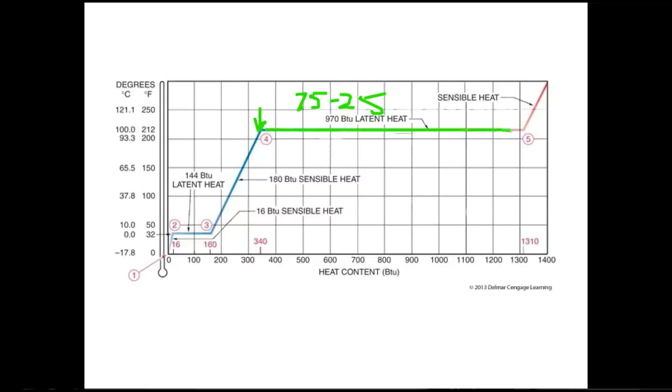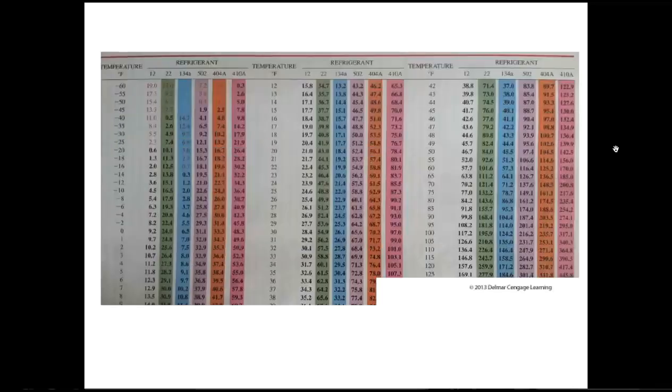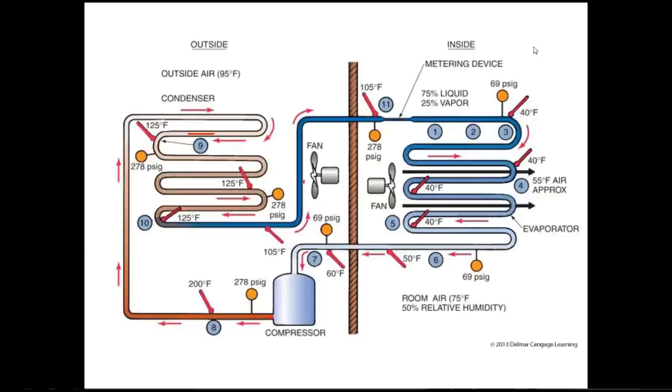And at this point in our evaporator coil that we just looked at, we're now at 100% vapor, and any heat that's gained is sensible heat, and that is our superheating point right here. There is really no cooling that happens with the superheat. We have superheat to make sure that we have 100% vapor going back to the compressor.